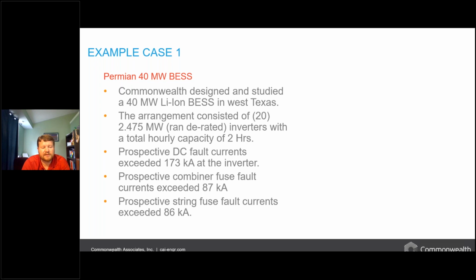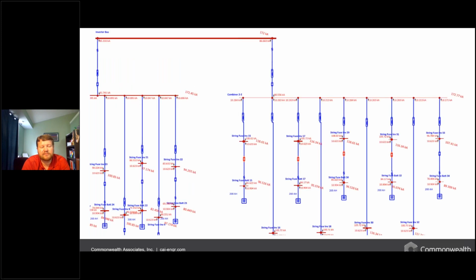So on this next slide, I have an example. This is coming out of our ETAP software program. This is a steady state program that looks at the potential maximum DC fault currents. And what we're finding is we're seeing very, very high DC fault currents. And just to give some perspective, if we talk about some of the most challenging AC fault currents in the entire Eastern interconnection, generally between 65,000 amps and 80,000 amps is considered extremely, extremely high fault currents, and a very, very high magnitude. It's very difficult to find equipment that can handle a fault of this magnitude. And what we're seeing for our DC system, we're seeing DC fault currents that are up to 2 times that number. So at our inverter bus, we're seeing fault currents of up to 172,000 amps.